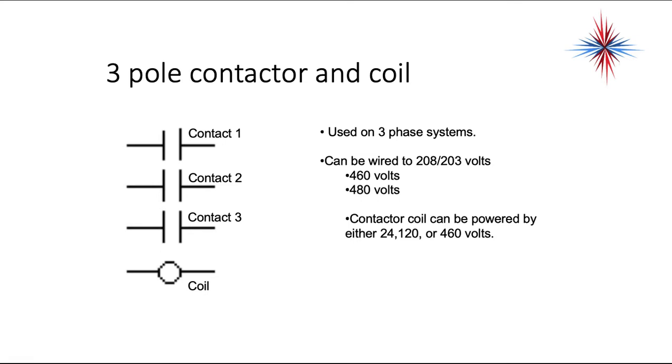Three pole contactors most often are used on three phase systems. You don't see that often on gas heating unless it's a big rooftop unit. They can be wired to 208, 460, 480. The contactor coils can be powered by 24, 120, or 460 volts. You'll always want to look at the stamp on the side of the coil on the side of the contactor and make sure you have the right voltage on the coil.